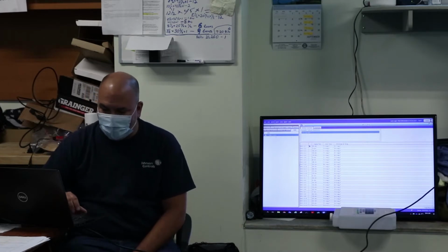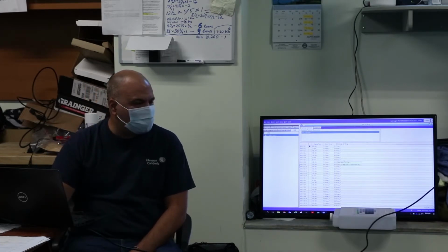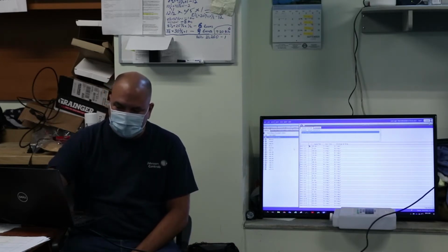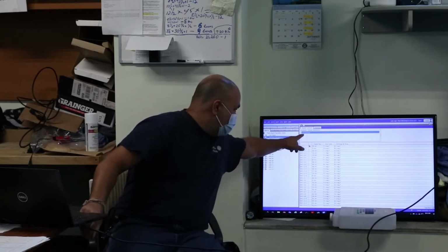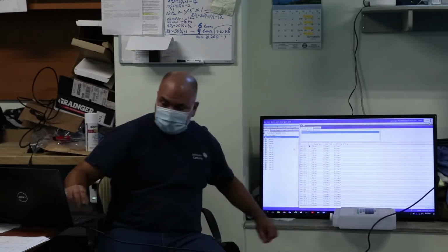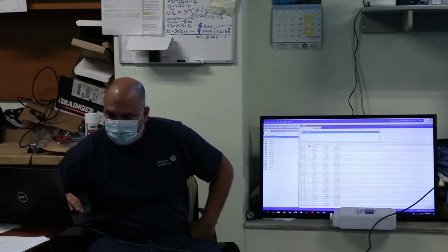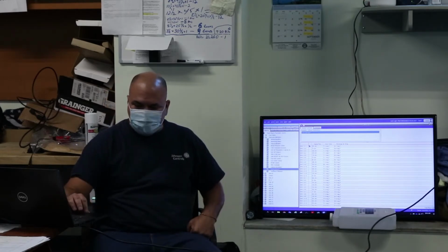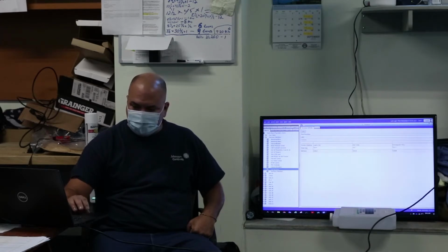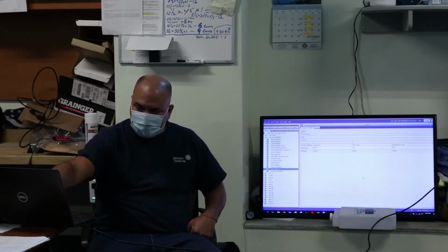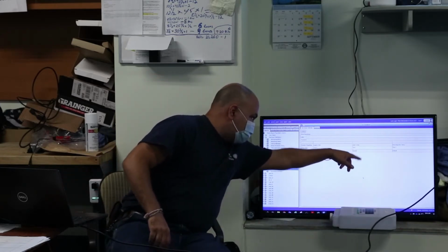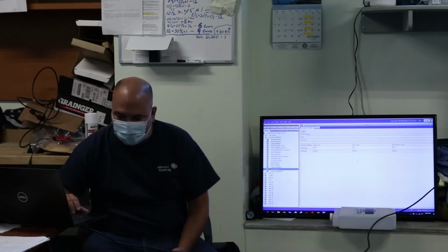Now if we wanted to add, I think we could add up to 7 items on this. So we'll go back to the all item list and see where it says summary definitions, right? The name is VAV summary, so we're going to look for that in the summary definition form. Right down here, we have it. We'll double click on it, and there are the properties that we're reading: the supply air flow, the zone temperature, and the discharge air temperature. So let's add another property in there.